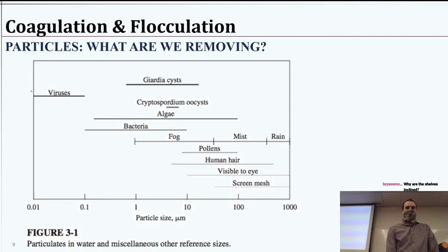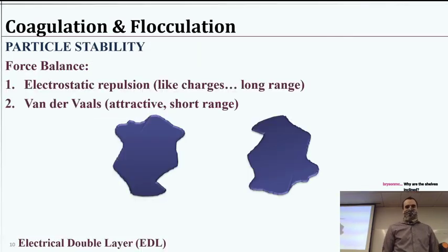Viruses are going to be way too small, but perhaps if we cause them to stick to some other larger particles, we may remove some of them. So ultimately, this is not a disinfection process. We're not capable of that level of treatment with just sedimentation, but we're getting to the point where we can remove a fair bit of the algae and some of the stuff that these pathogens may stick to.